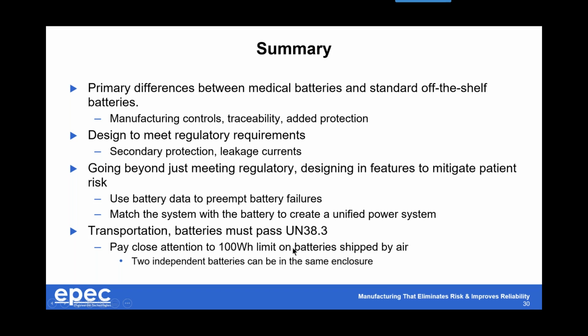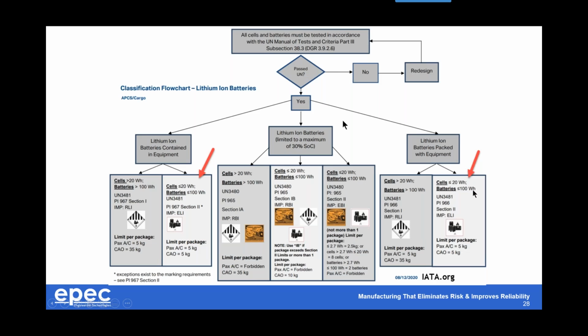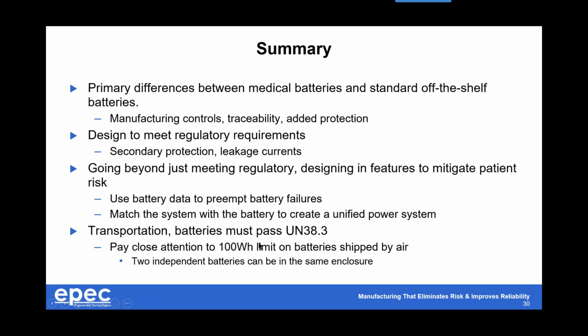And then we just touched a little bit on the batteries. As I reiterated many times, it's got to pass UN 38.3. If it doesn't, you're not going anywhere. And then also pay close attention to the 100 watt-hour limit. If you notice in the slide, a couple of slides back, all this right here, less than 100 watt-hour. If you want to take a battery on an airplane, you really need to pay attention to that limit. And a lot of times your design decisions will impact what that is. Sometimes we'll put two independent batteries in the same enclosure, each one being 100 watt-hours, and that seems to work quite well, as long as they're electronically independent.